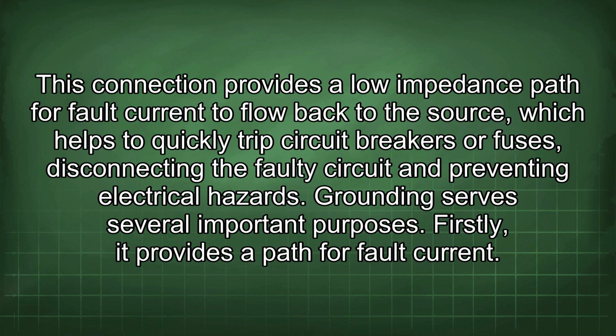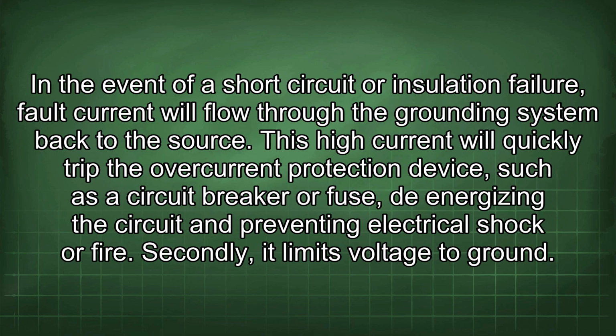Grounding serves several important purposes. Firstly, it provides a path for fault current. In the event of a short circuit or insulation failure, fault current will flow through the grounding system back to the source. This high current will quickly trip the overcurrent protection device, such as a circuit breaker or fuse, de-energizing the circuit and preventing electrical shock or fire.